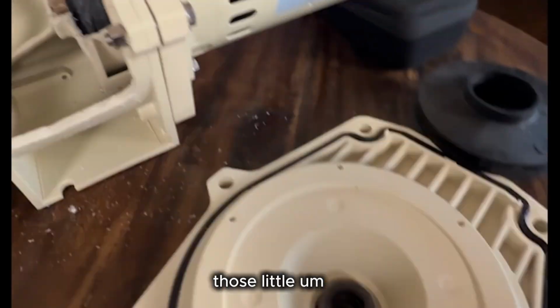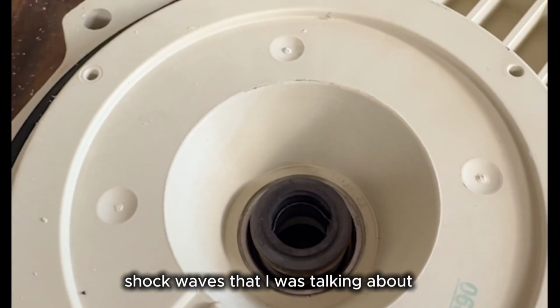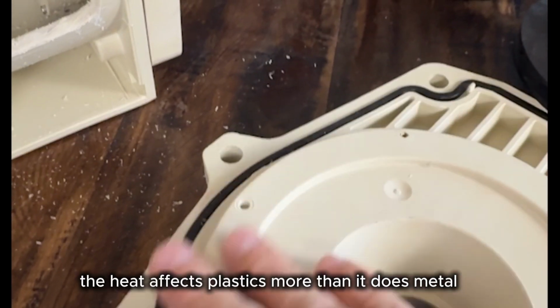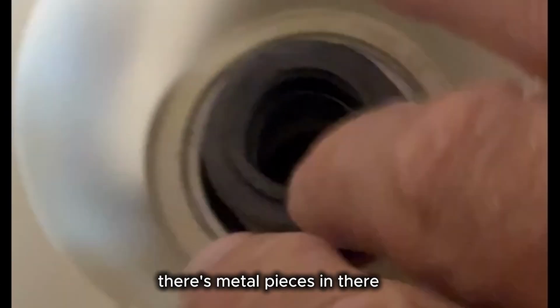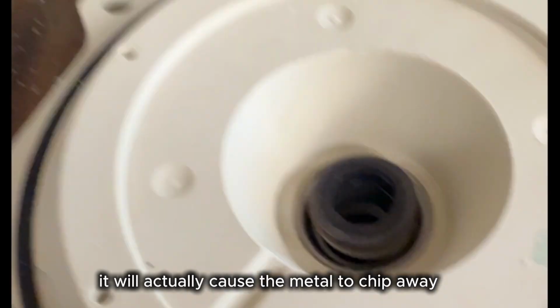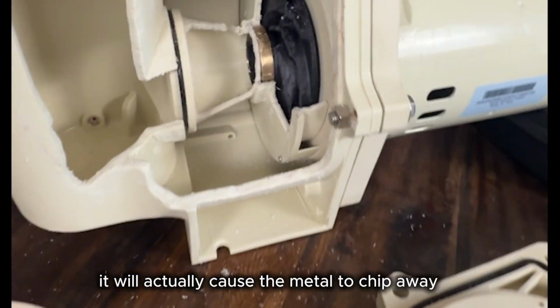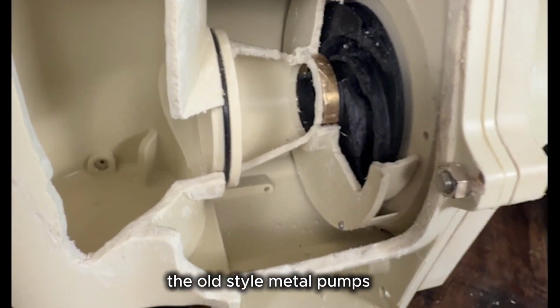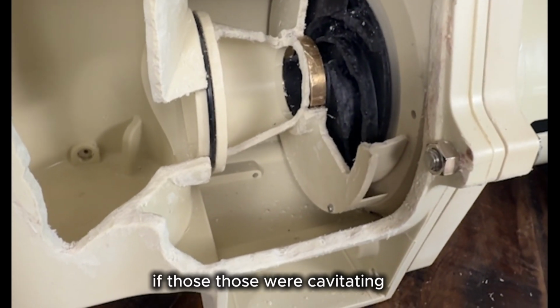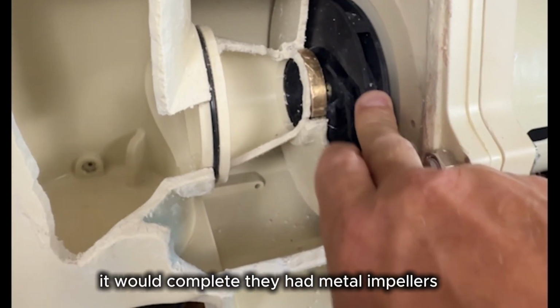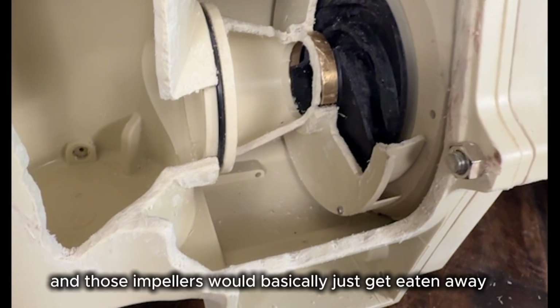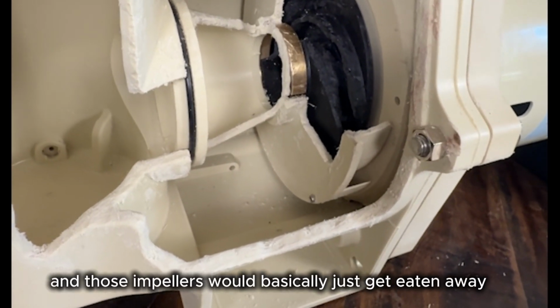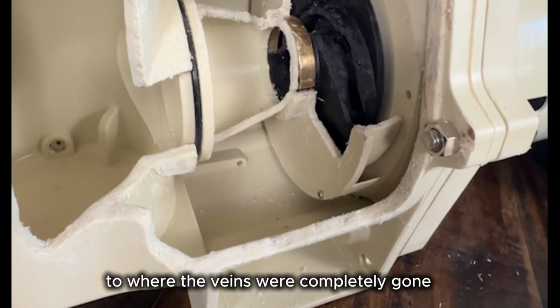Those little shock waves that I was talking about, and that heat, the heat affects plastics more than it does metal. But on those shaft seals, there are metal pieces in there. If these little shock waves are hitting this metal, it will actually cause the metal to chip away. The old style metal pumps, if those were cavitating, they had metal impellers, brass impellers, and those impellers would basically just get eaten away to where the vanes were completely gone.